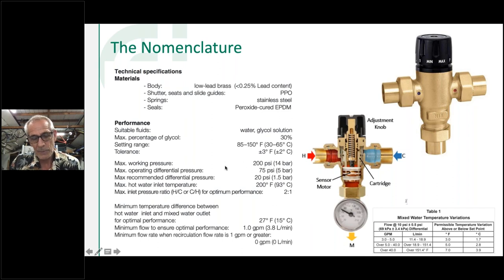There's also the maximum inlet pressure ratio — the question comes up: why would pressure be different on each side if you have 60 pounds of water pressure? Here's where it comes into play most often in tech support calls: people with a boiler and a tankless coil that starts to scale up. With a small opening in that scaled coil, even with 60 psi coming in, opening multiple faucets means the hot side pressure drops based on the restriction in that coil. The same can happen if a restaurant has a high-temperature takeoff before the mixing valve and runs a commercial dishwasher.